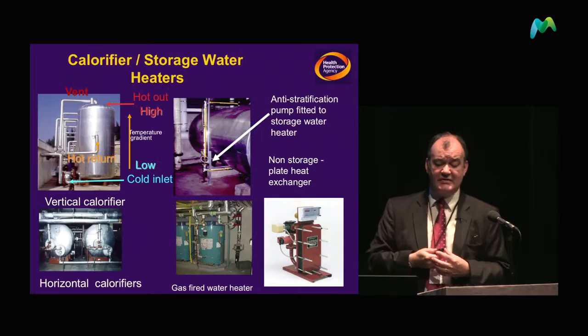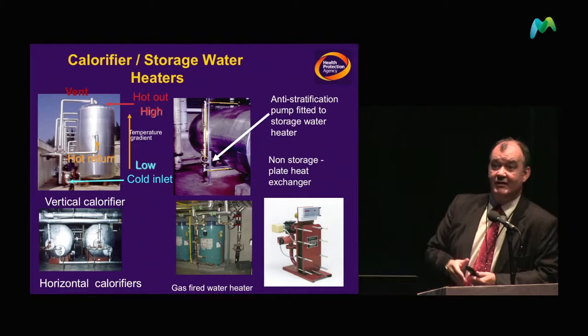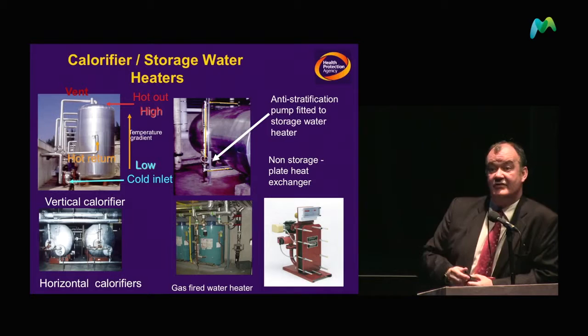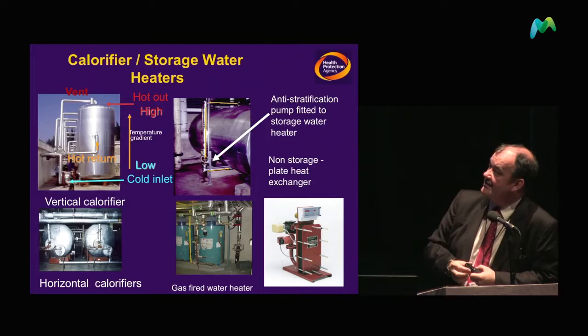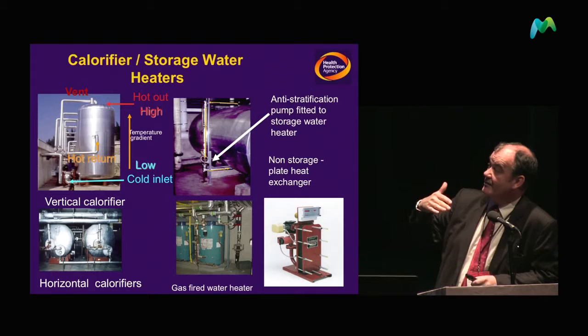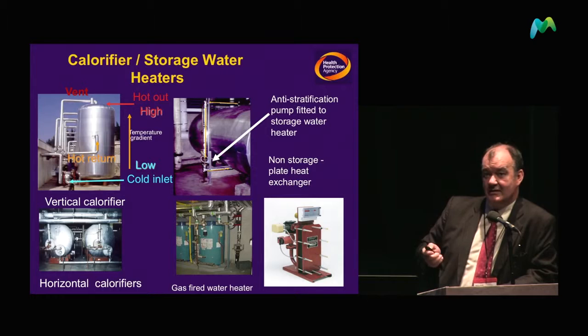In terms of design — when you've got a large hot water tank there is a tendency for all the cold water to collect at the bottom. One of the remediation measures is what we call an anti-stratification pump, which circulates the water from the bottom of the tank to the top. A tank without this has a potential problem because you will get an optimum temperature zone where Legionella would grow, and it's not uniformly hot throughout.